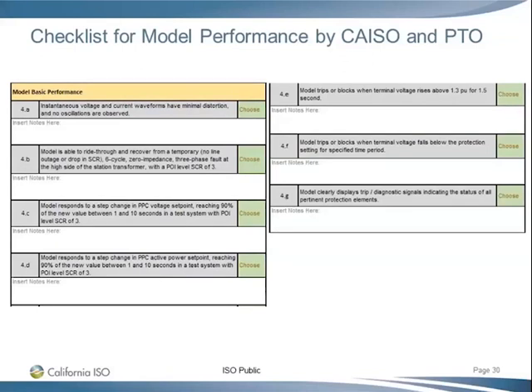So continuing with the performance test by ISO. You see here that this is the checklist I mentioned earlier. This one is a little bit different from the ones we showed before. On the left side, that's where the generator owner will answer. Actually now you don't answer anything. It's only the right side, where the PTO and ISO will choose yes, no, or not applicable. So we'll run those tests, and you know what we run, and you can do the same thing yourself.